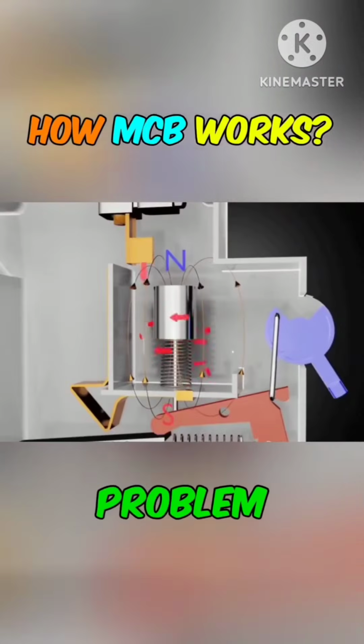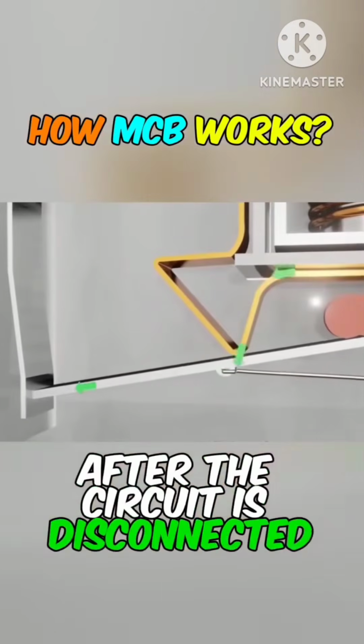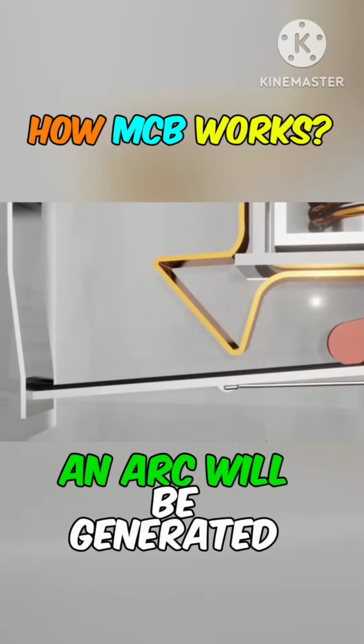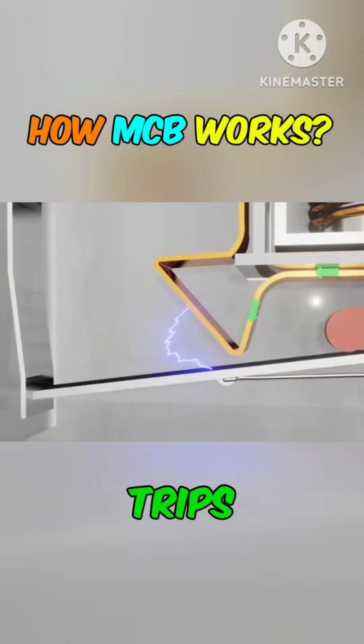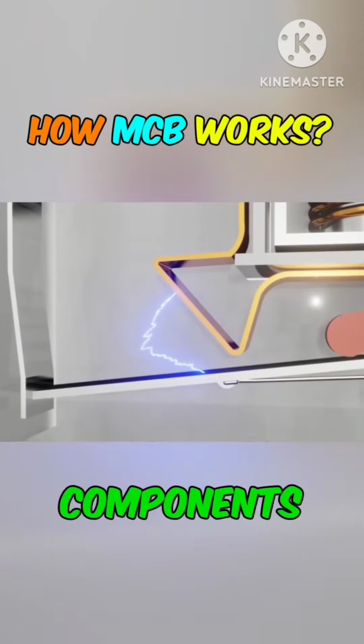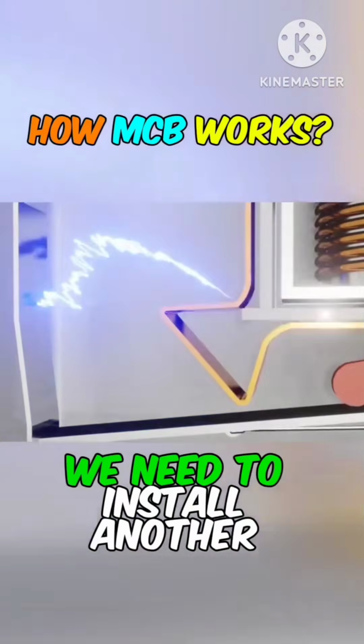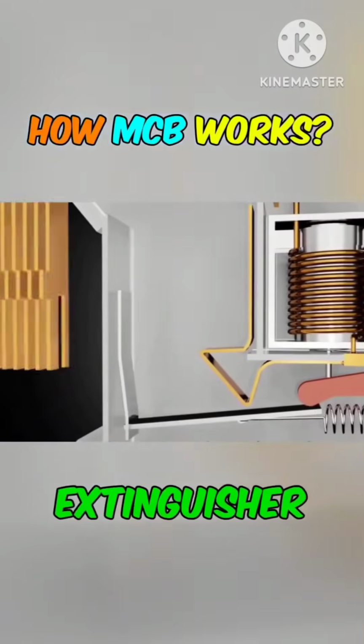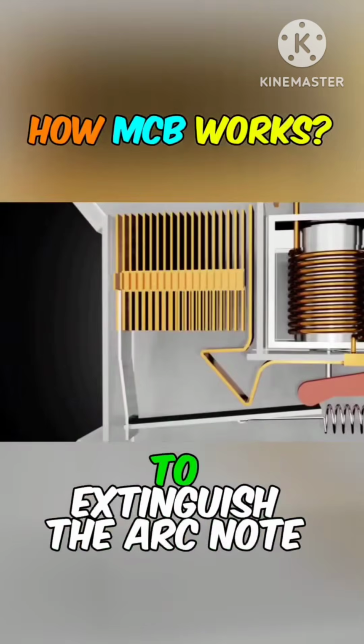However, there is still a problem after the circuit is disconnected. If the current is strong enough, an arc will be generated when the circuit breaker trips, potentially damaging the components inside the MCB. Therefore, we need to install another extinguisher, which can channel the arc into it to extinguish the arc.